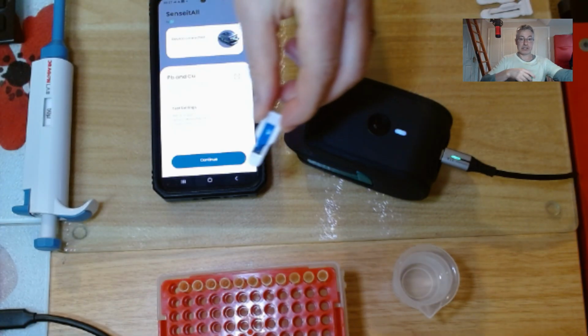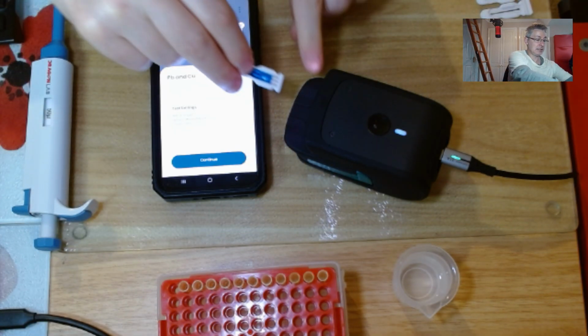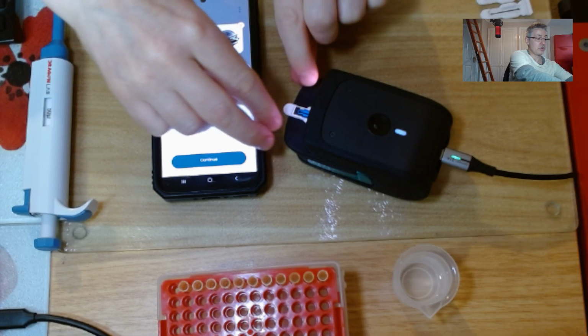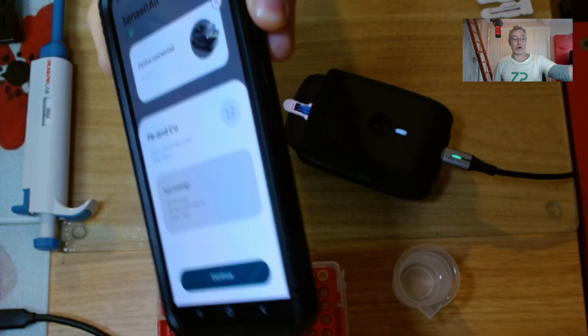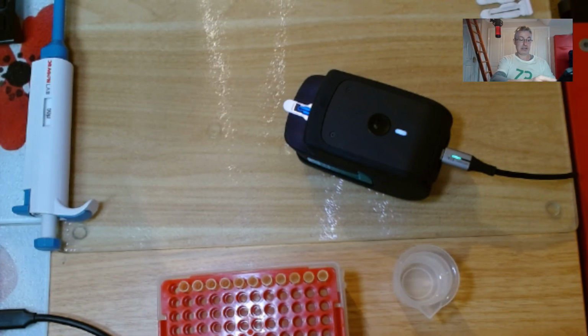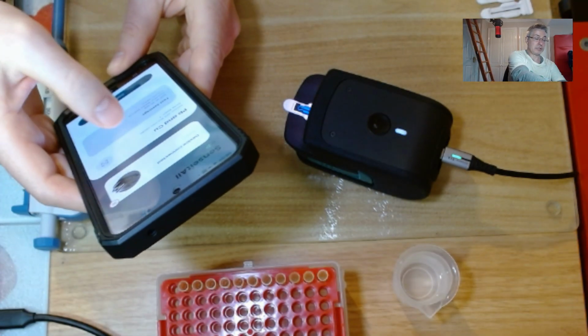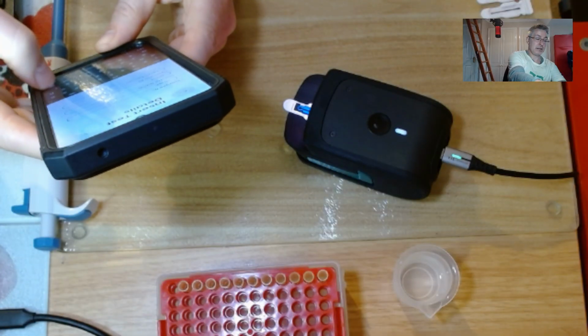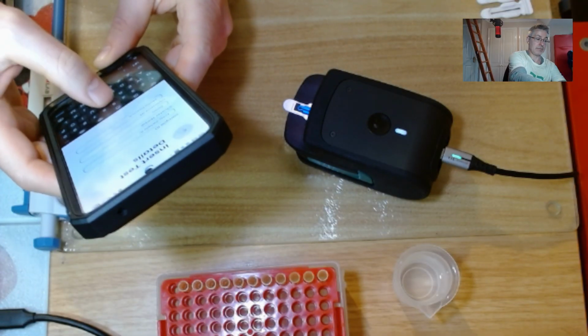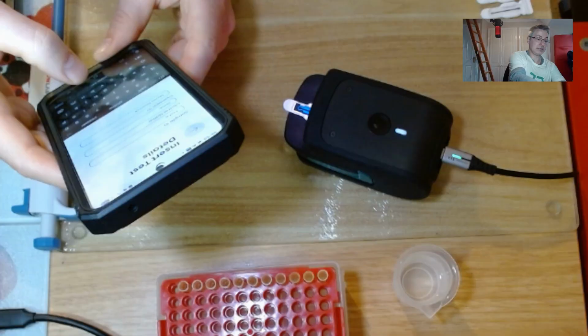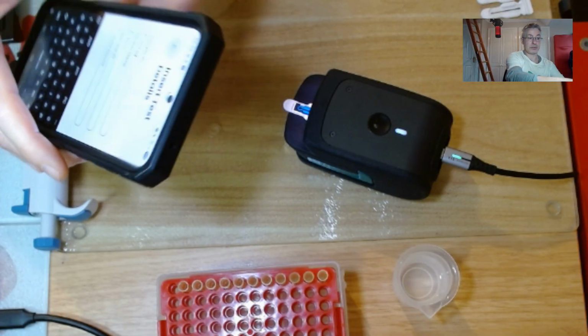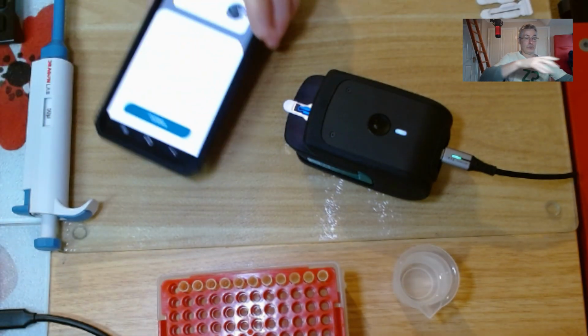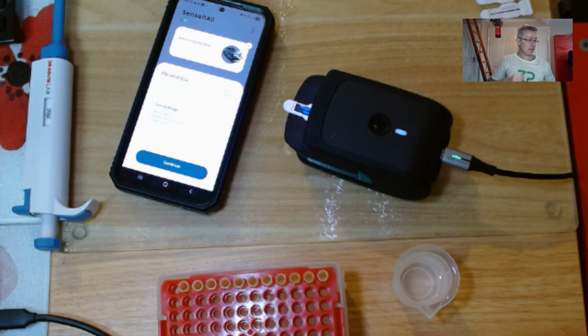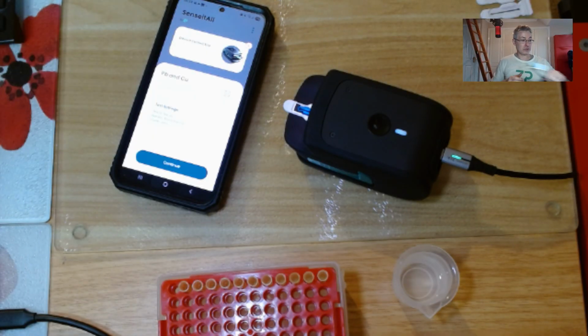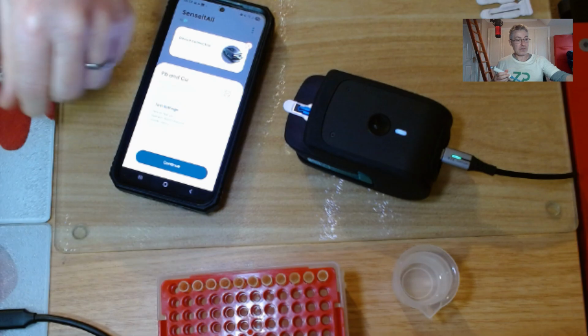So I'll take the sensor, it's one sensor per test. The new QR code, when I scan it now, means that this is a copper or lead and copper assay at the same time. And I'm going to give this sample a name. So I will put test lead. I'm going to put test lead in this.